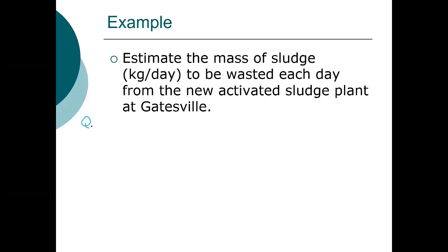So we have Q waste is equal to V times X over the mean cell residence time divided by the VSS in the recycle line. So this is our VSS in the aeration tank, and this is our VSS in the return activated sludge line.